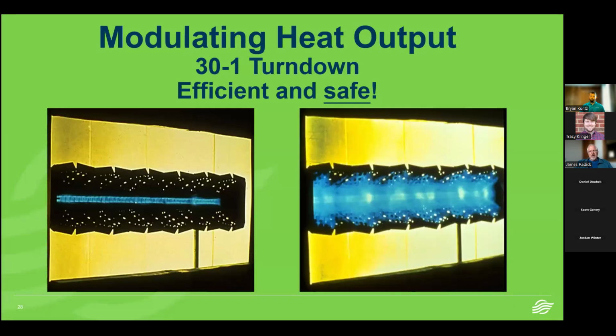But again, you're going to activate, turn on and modulate the burner. Well, your car has a gas pedal, right? And cruise control, et cetera. It modulates the energy being produced by the engine. This is how we do it with an air handler. We have a modulating burner. It's a direct fired burner. Don't be concerned. There are still folks out there that are concerned over direct fired burners. They see the flame in the airstream, which is great because you're getting 100% of the heat produced by the flame delivered to the space. You can't get any more efficient than that.